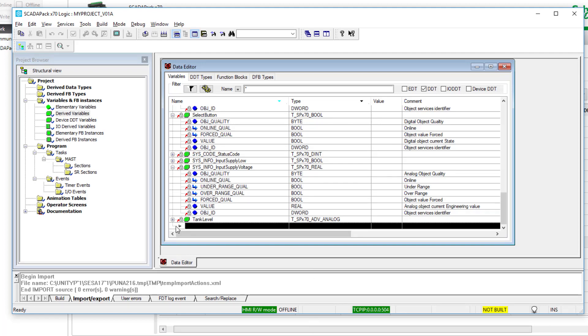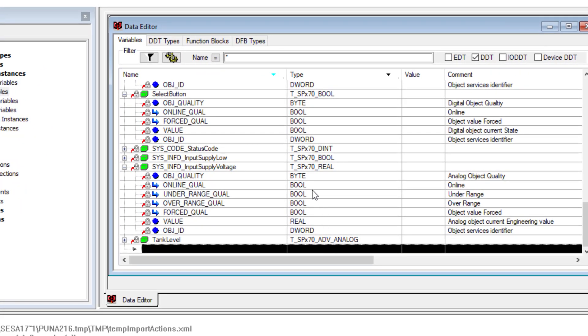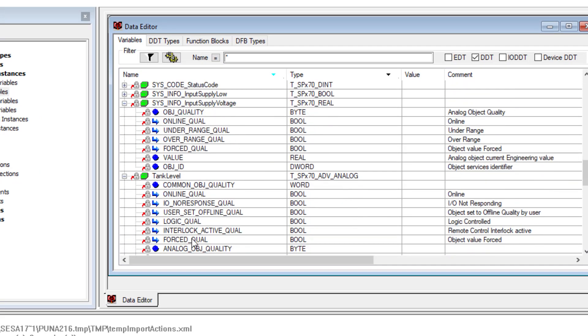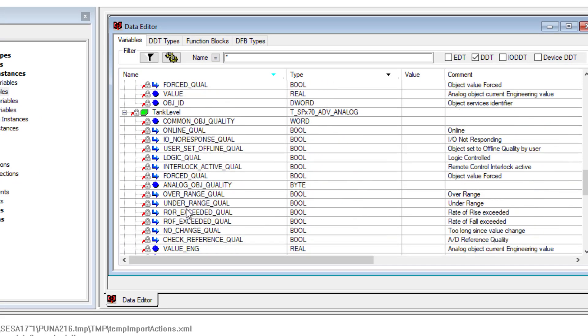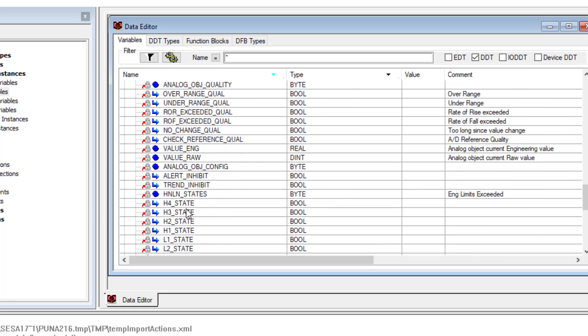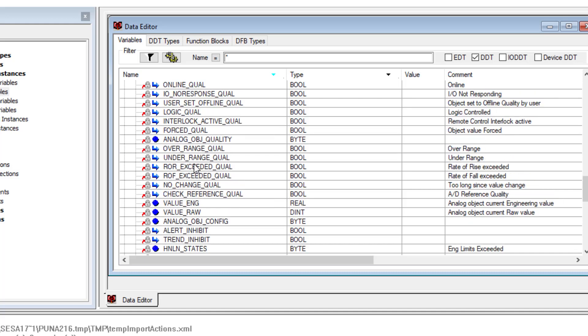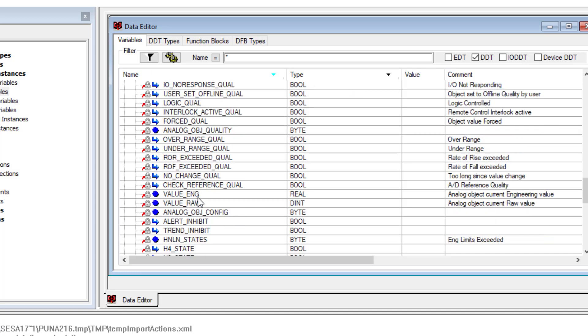If we select the advanced analog in Unity, now the type of object has changed and here are all the remaining properties, and there's quite a lot of them. Here's the under and over range. These are all the object quality values. There's the no change quality as well as the rate of rise, rate of fall.